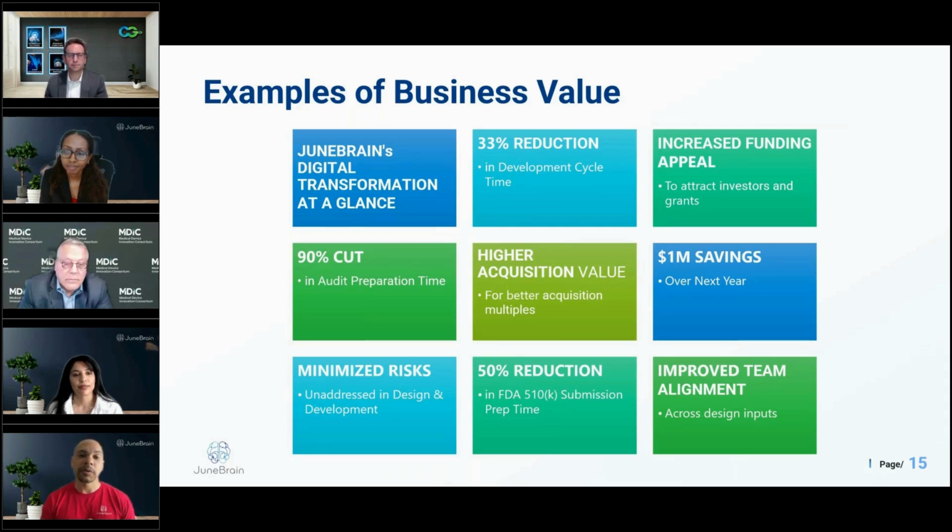So our clinical research manager said, "Maybe we can do a feature where we have a stoplight. As you are starting to focus the eye, it'll have a green indicator to let you know that this is good quality." So she went back into Polarion and added that into the system. We now have an official requirement, and we've already implemented it. Our current version of the device has a green quality indicator to let the operators know that the image is good to go. We can do this for future feedback. All the teams are on the same page, so we can understand that requirement and what the specs are needed to close that out.